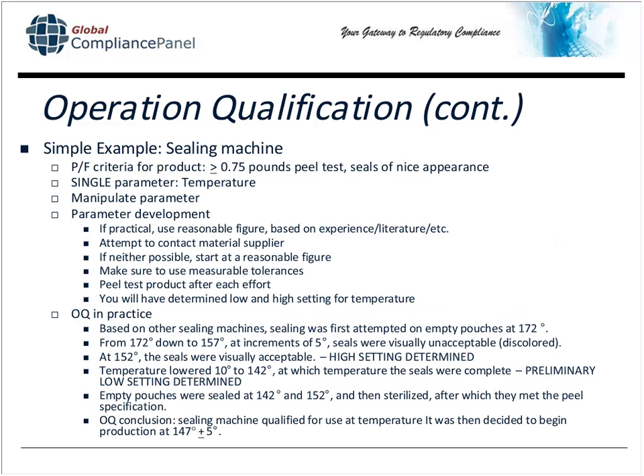Here's an example of a sealing machine OQ. Again, kind of cursory here, but for a simple example of a sealing machine, here's my pass-fail criteria. A certain amount of peel test strength, and my seals have to look good. Obviously, it says nice appearance here, but I'm going to have perhaps visual acceptance criteria that I include as part of this protocol. I have a single parameter for the purposes of this simple example. Again, this is a very simple example here. And my only parameter is temperature. So I'm going to manipulate this parameter.